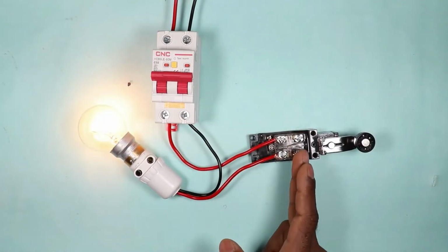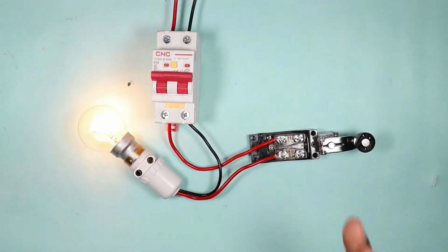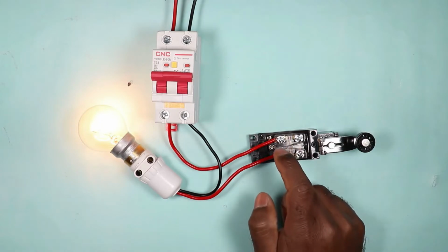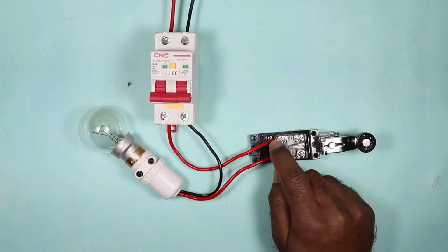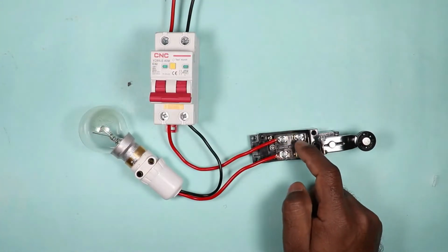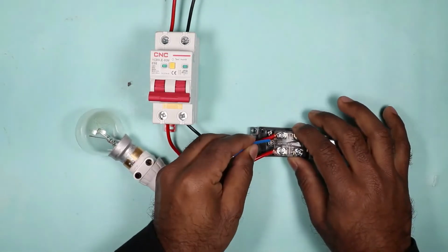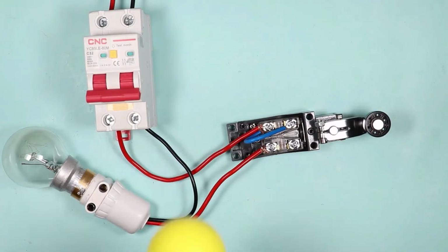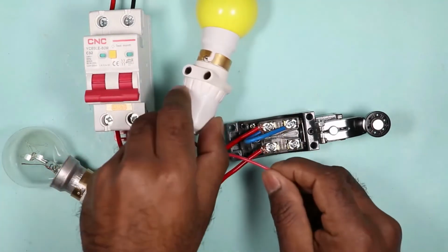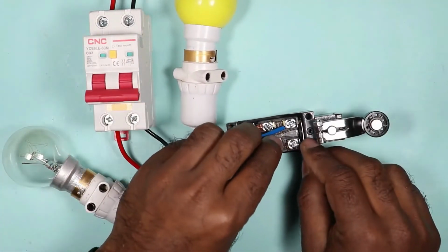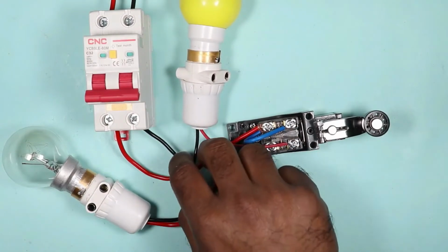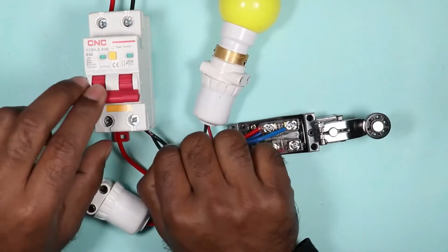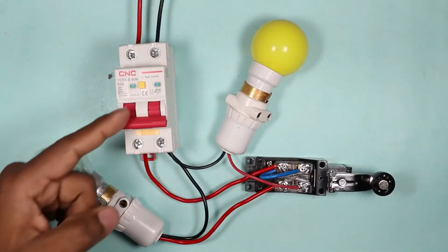Till now I explained about NO and NC contact. If you want to use both the contacts together, NO as well as NC, the phase supply wire to NC is to be looped with NO contact. So I am using a wire to supply power. To show the output signal from NO contact, I am connecting one more lamp. The phase wire is to be connected with NO contact and we will directly provide the neutral power supply. The connection is now completed, so I am turning on the MCB.